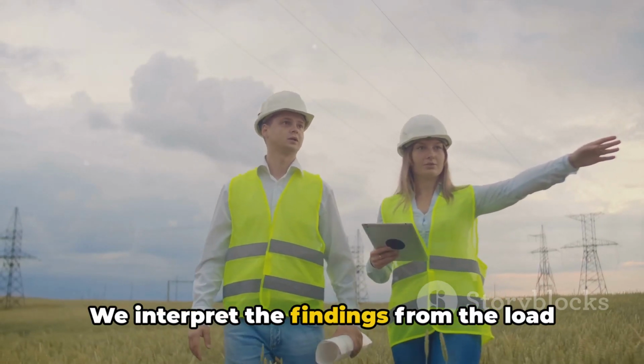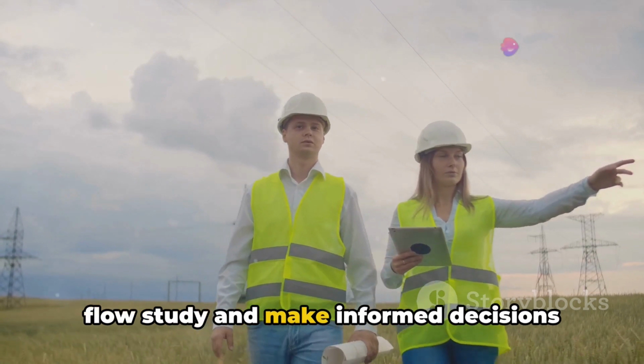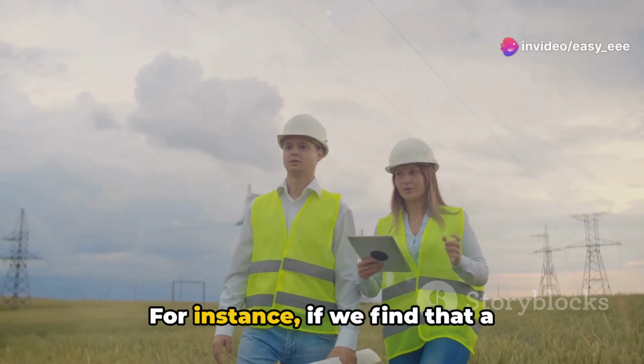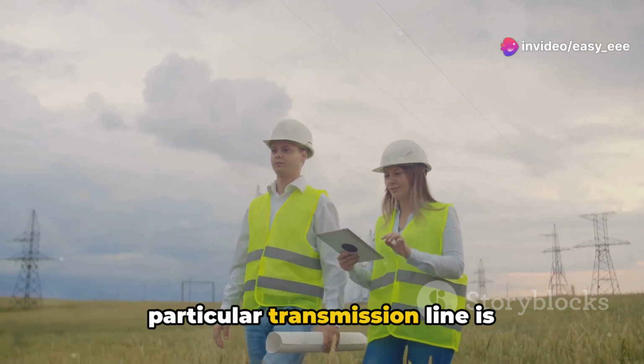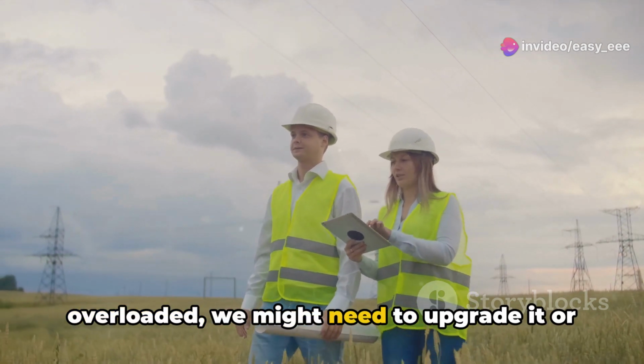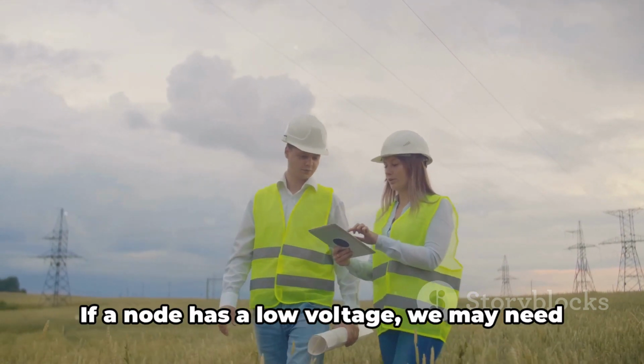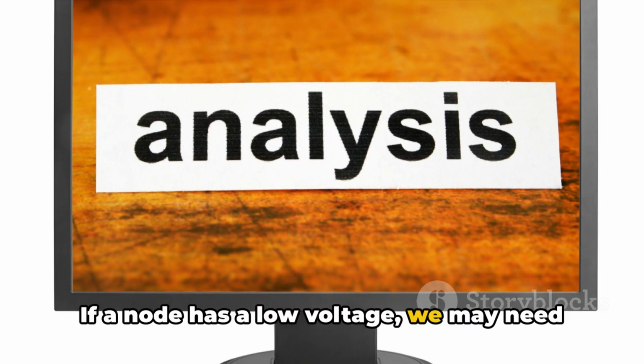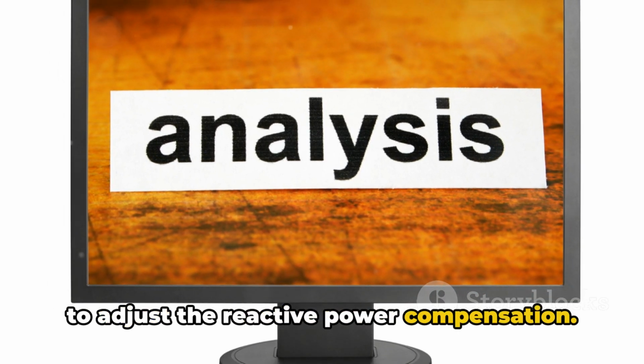The final step is the analysis of the results. We interpret the findings from the load flow study and make informed decisions based on them. For instance, if we find that a particular transmission line is overloaded, we might need to upgrade it or reroute some of the power. If a node has a low voltage, we may need to adjust the reactive power compensation.